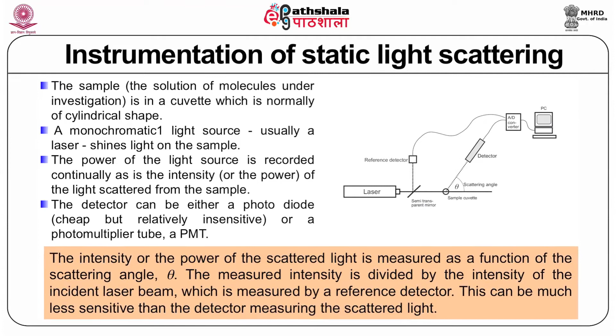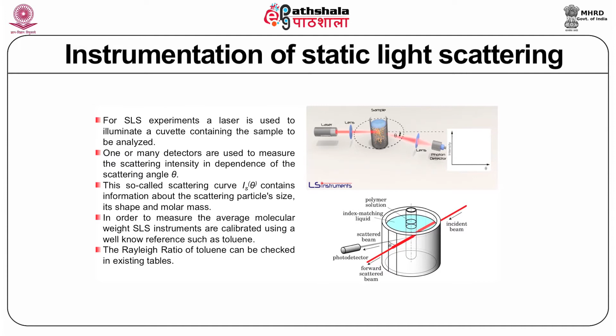So, the intensity of the scattered light is measured as a function of the scattering angle, that is theta. The measured intensity is divided by the intensity of the incident laser beam, which is measured by the reference detector. This can be much less sensitive than the detector measuring the scattered light. Here I try to show you the process of SLS in the form of an animation. You can see here how the laser light passes through a monochromator and is incident on the sample, and then it is scattered in all directions, where we can measure the intensity of scattered light at different angles.